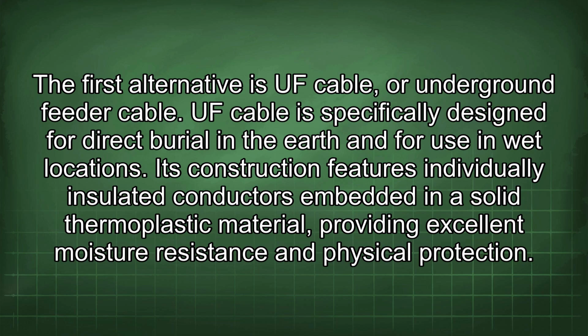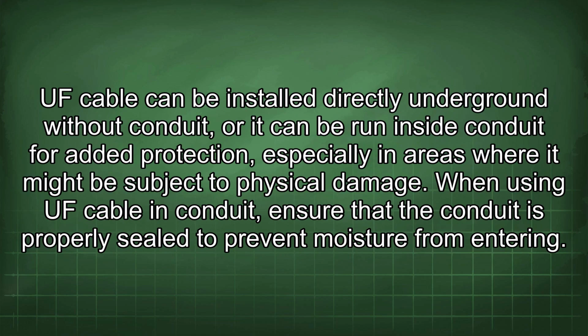The first alternative is UF cable, or underground feeder cable. UF cable is specifically designed for direct burial in the earth and for use in wet locations. Its construction features individually insulated conductors embedded in a solid thermoplastic material, providing excellent moisture resistance and physical protection. UF cable can be installed directly underground without conduit, or it can be run inside conduit for added protection, especially in areas where it might be subject to physical damage. When using UF cable in conduit, ensure that the conduit is properly sealed to prevent moisture from entering.